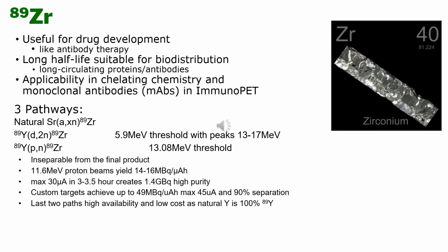There has also been research into custom liquid targets, but they result in a much lower yield and therefore are only used where solid targets cannot be utilized due to workspace limitations, and the required zirconium-89 to be produced must also be low.